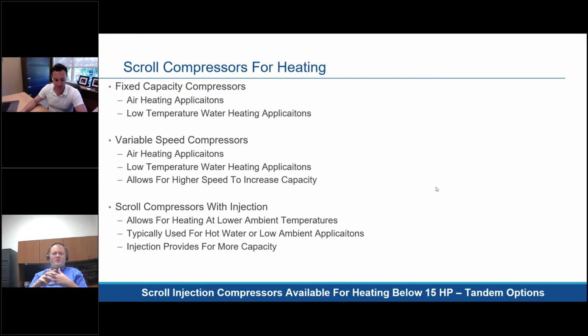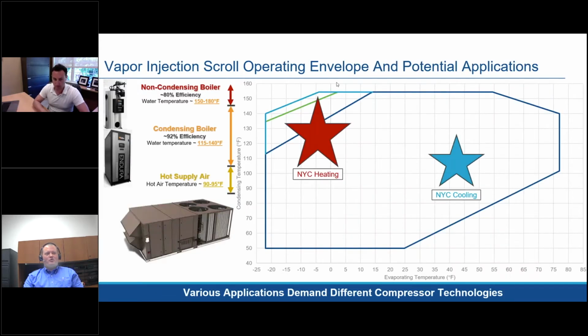Yep, I'm going to go here in the next couple of slides, but really what vapor injection is, we're taking some refrigerant from the liquid line, and we are routing it back to the compressor and injecting it right into the scrolls to help keep those scrolls cooler. Because, I'll go back up to this next slide, as you start running up on the upper left side of the envelope, which we consider high compression ratio conditions, that increases the discharge temperature. Compressors can only handle a certain level of discharge temperature. So we will want to directly dump that vapor injection, or a mix of vapor and liquid, or pure liquid, into the scrolls in order to cool them so they can operate up in this top left region.